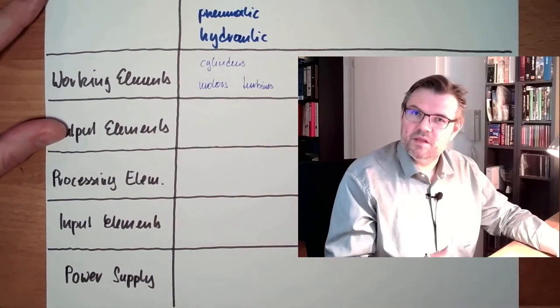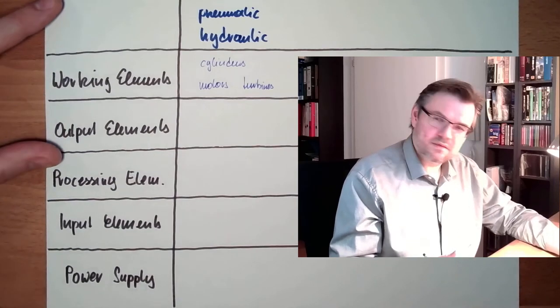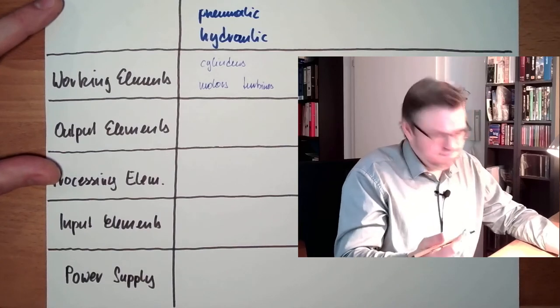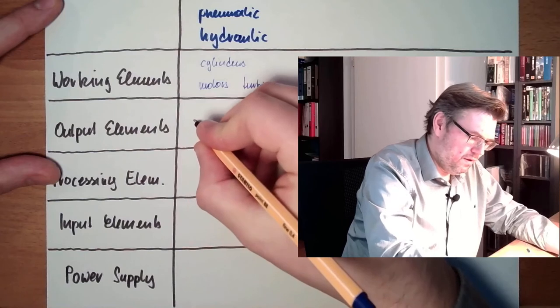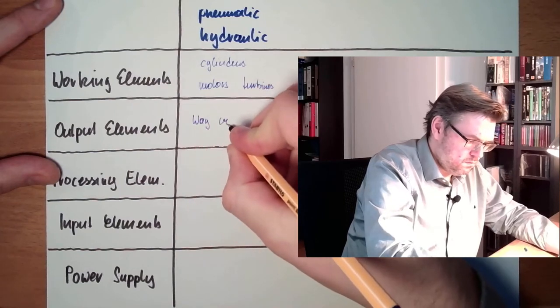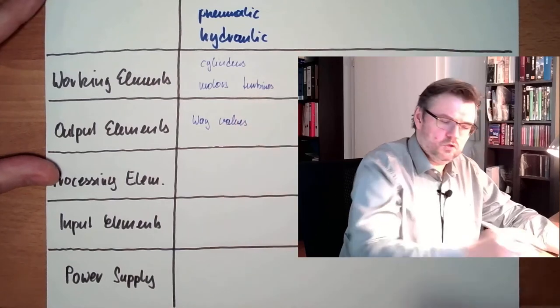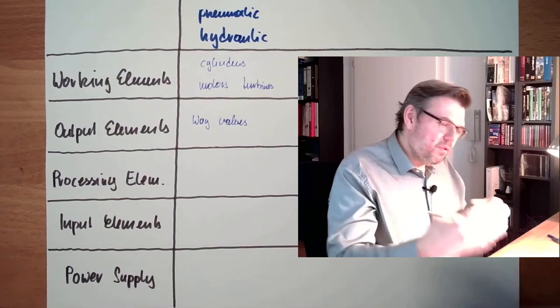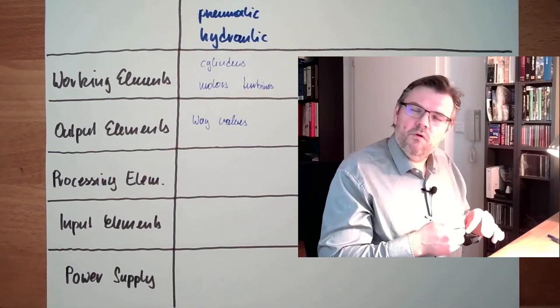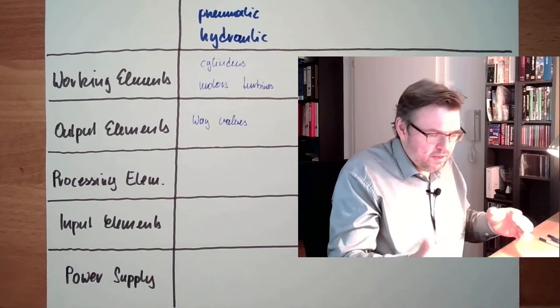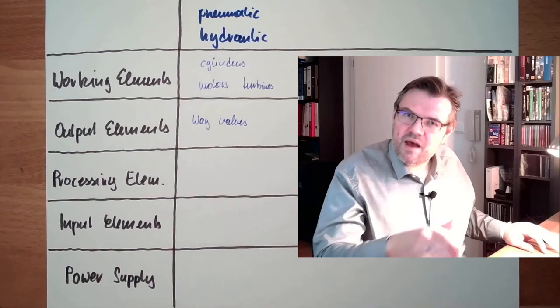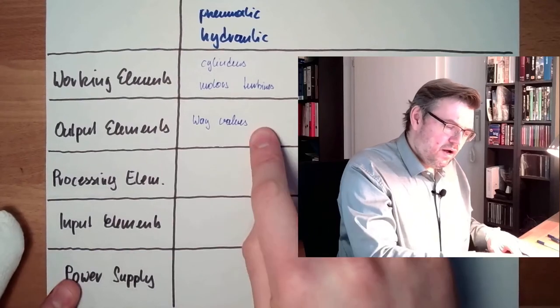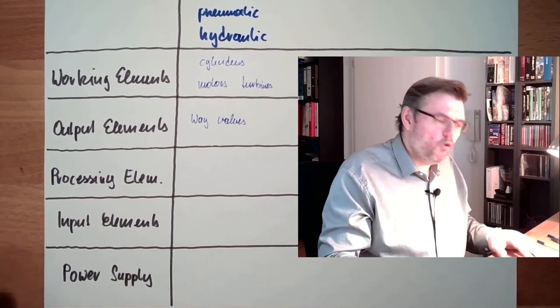These are the working elements. Output elements, typical output elements are way valves. There is hardly more, way valves. A single acting cylinder needs a 3-2 way valve, a double acting cylinder needs a 4-2 way valve or a 5-2 way valve, depending a little bit. If it's pneumatic, usually it's 5-2, in hydraulic, usually it's 4-2. So way valves, big enough, big way valves, big enough to control the working element.